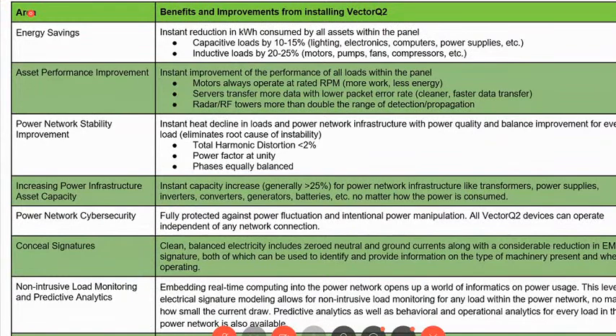And then finally, the non-intrusive load monitoring and predictive analytics. By embedding real-time computing into the network and identifying the differences among electrical signatures and tracking those signatures over time, now you have full historical visibility of all of the assets within a network and the deviation over time. A deviation in an electrical signature is nothing more than the internal components wearing out or no longer working the way they were. It is the closest, the root visibility into changes in the network.